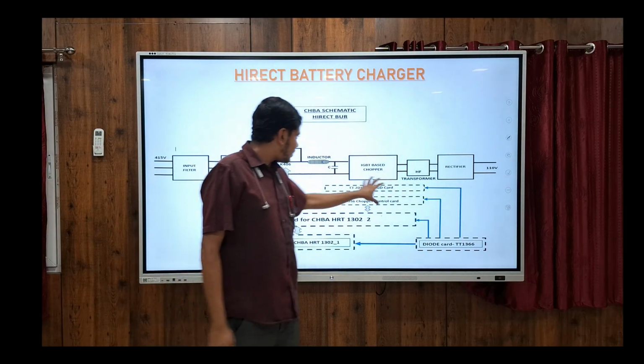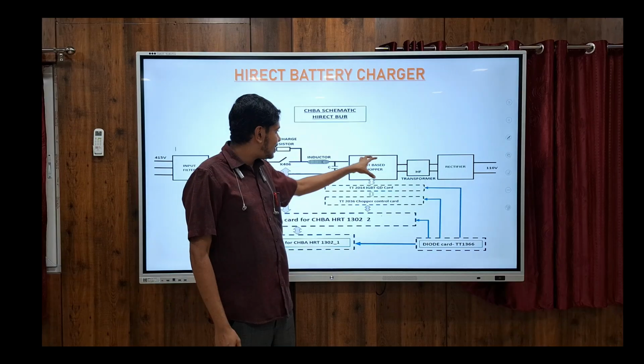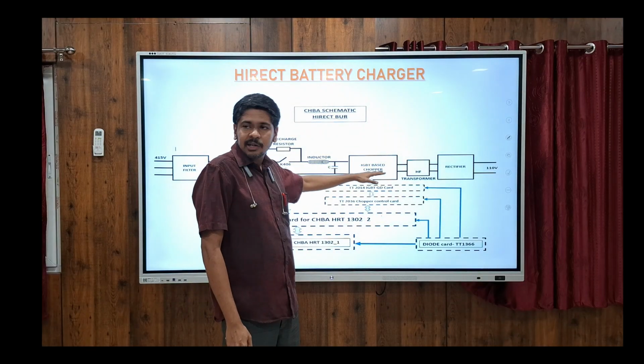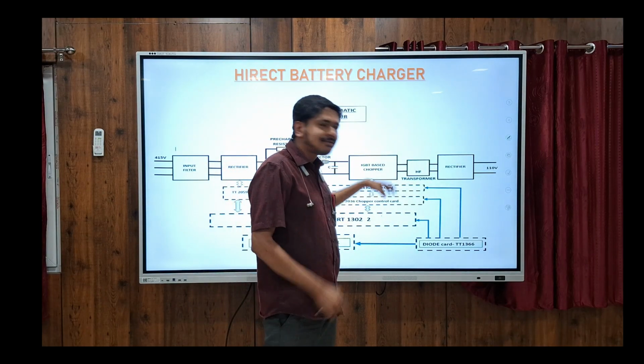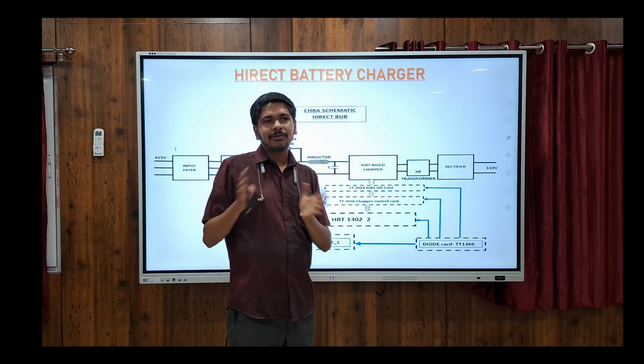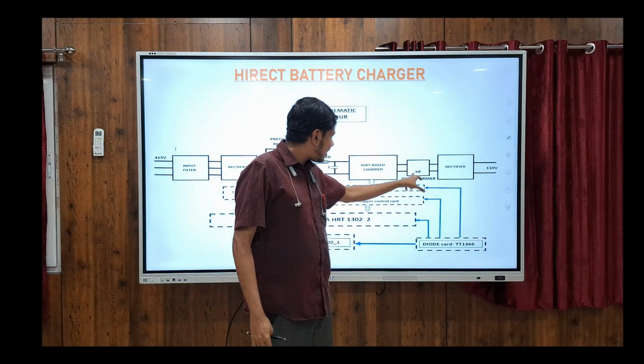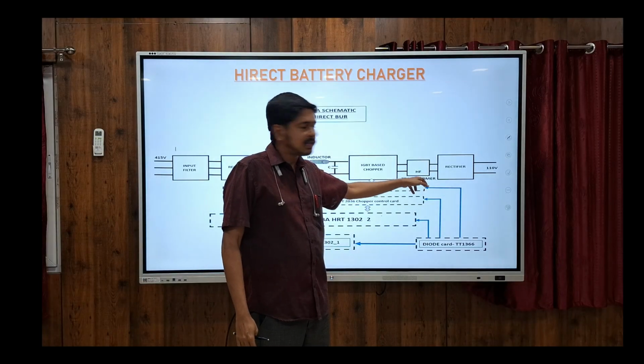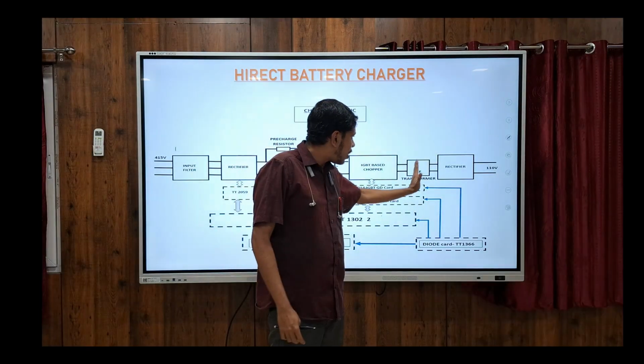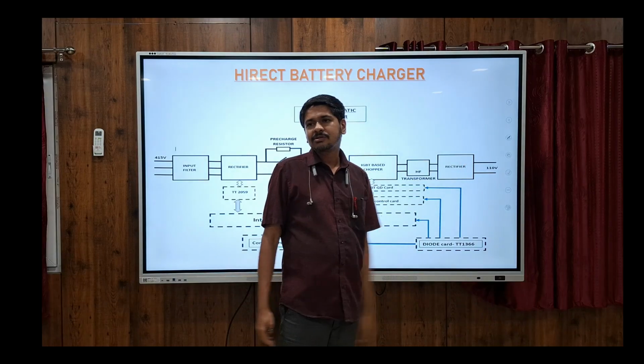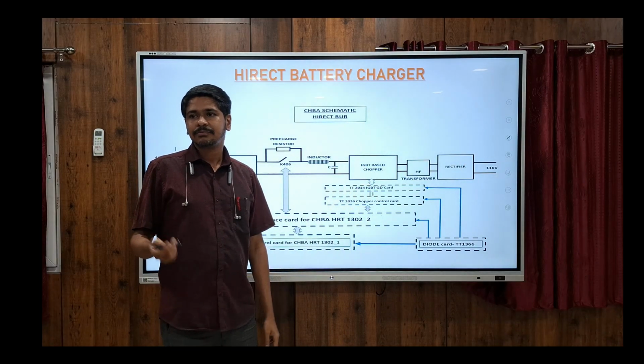After this, it will generate a high frequency pulsating DC, pulsating at 1.2 kilohertz. After that, one isolation transformer for galvanic isolation is provided, and its output will be rectified to produce 110 volt DC output.